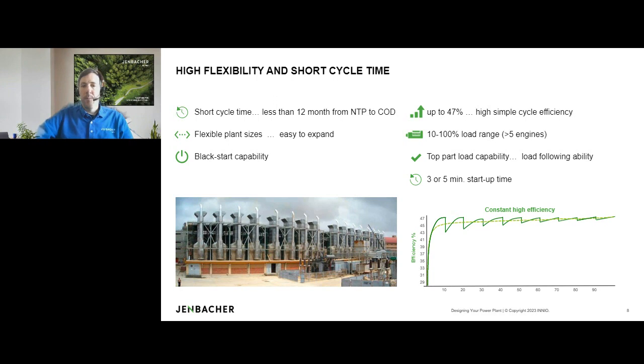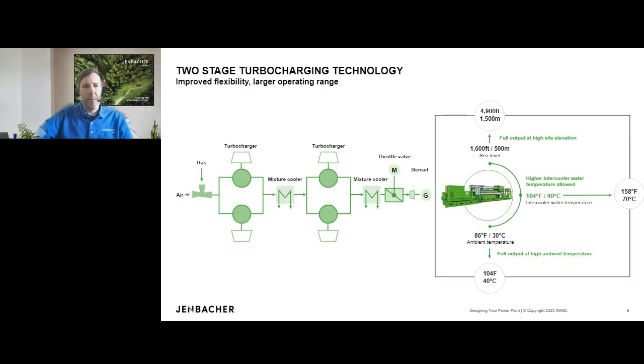They have the inherent black start capability, very high efficiency, and due to the use of multiple engines, you have excellent part load capability, meaning you can turn on and off engines as needed and always run the engines you are operating at very high load factors, meaning very high fuel efficiency. That's a major advantage versus a very large single shaft engine or turbine, which in part load would not have the optimum performance.